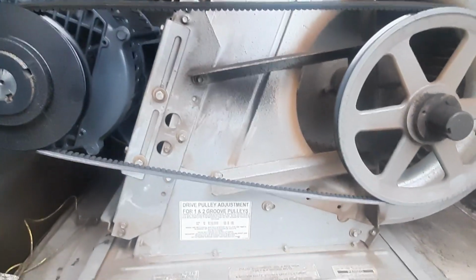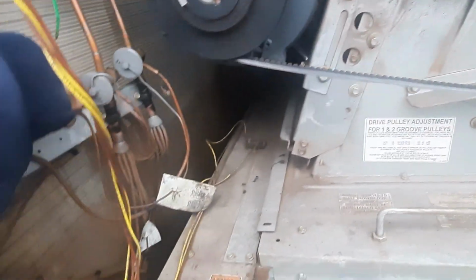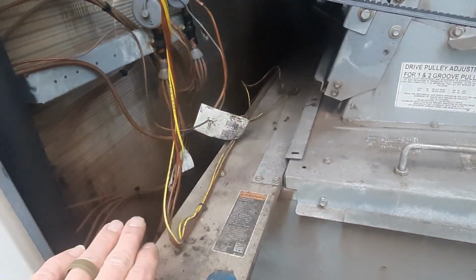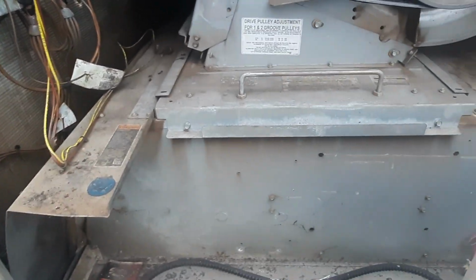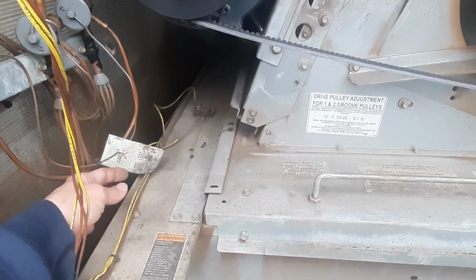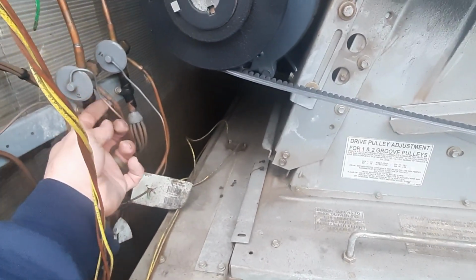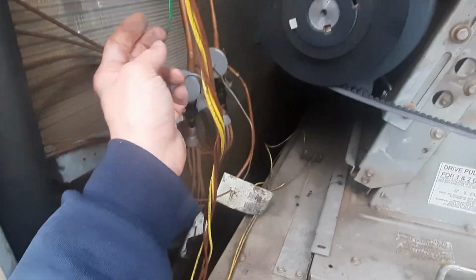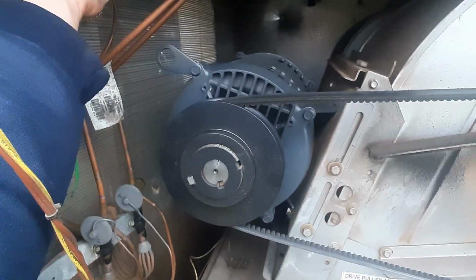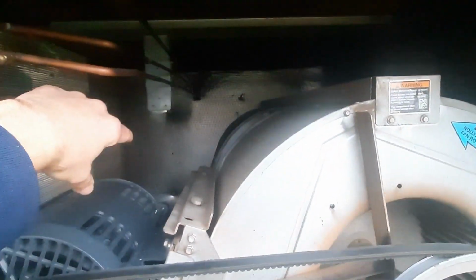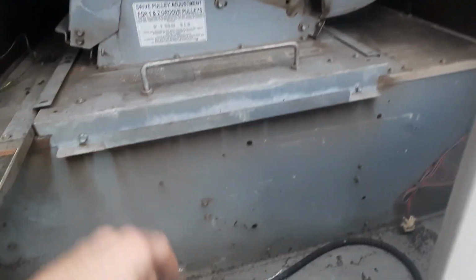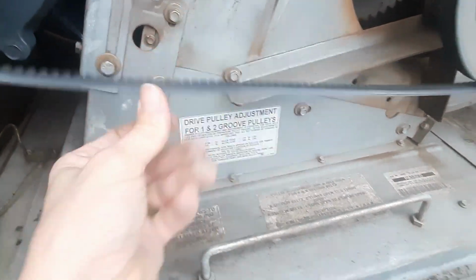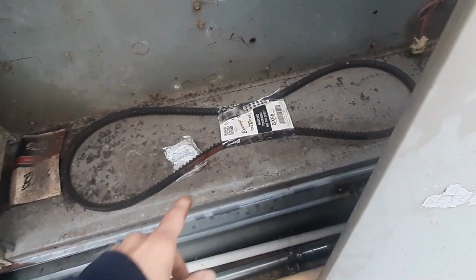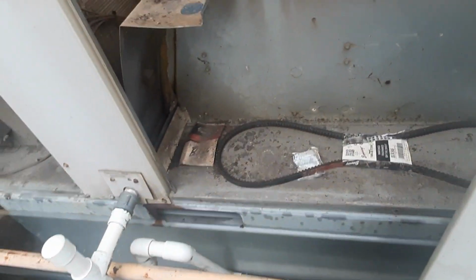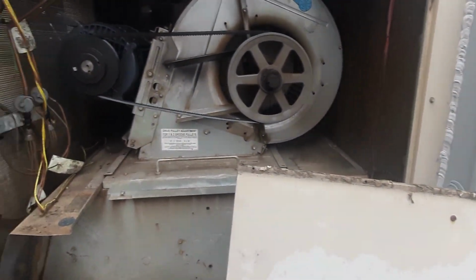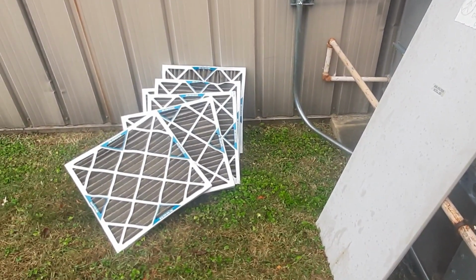I've been doing some work and some different trainings in the office. I'm going to leave all of this because I've got one of the younger guys coming out. We're going to go through this and do the maintenance on it. We're obviously going to need a new belt, but these are things, cap tubes rubbing, that I want to point out that we need to be catching when we're doing maintenance, because none of these should rub out, but they will. Everything back there looks pretty secure, but let's see. We got a nice crack in that belt too. Maybe we can throw the spare on for now. It's been over a year, so it's going to be time for the belt to go anyways. Let's get that done. We'll cycle the power back on. We ought to be okay for now, and then we'll go get some filters.